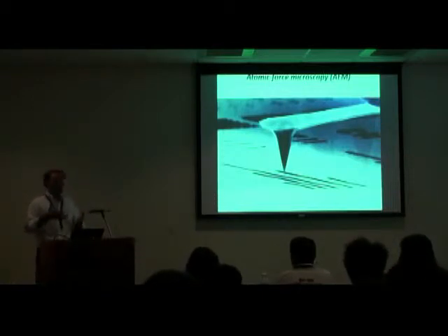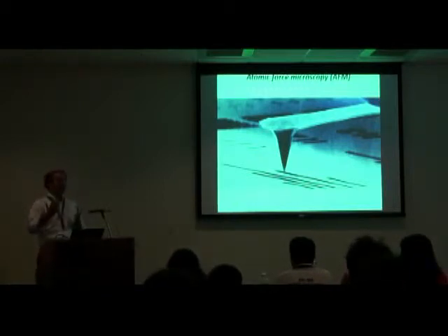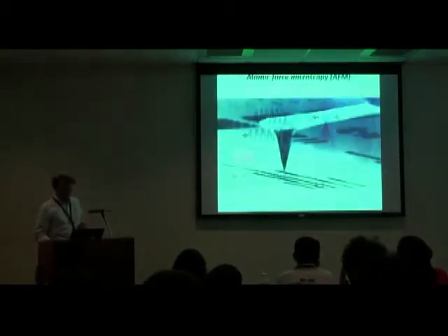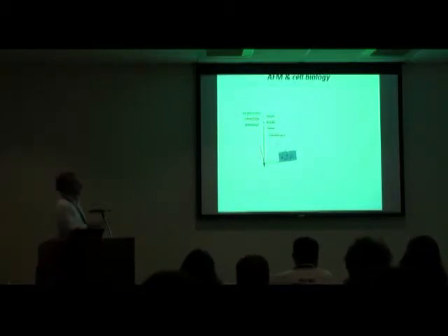And so now, with microfabrication tools, the cantilevers are now fabricated. They have tips with controlled sharpness, and rather than using an STM on top, we now bounce lasers off of them. So the current configuration that most people use for AFMs looks something like this. You've got a cantilever base that you can move in 3 dimensions. You've got a laser that's bouncing off of the end of your cantilever, and you've got some position-sensitive detector that allows you to sense what the displacement is, both how much it displaces vertically as well as laterally, if that's important for your measurement.